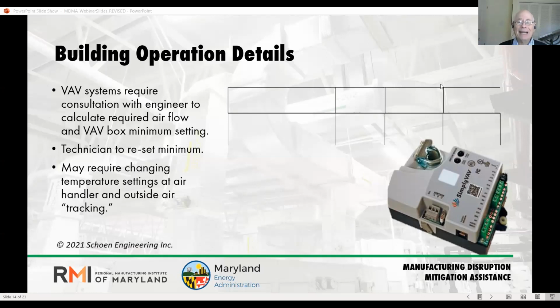It's important to have the settings on these never go to complete shutoff if the thermostat is satisfied. If you go to complete shutoff, that means you have zero ventilation in your room. That's not something we want. So in order to adjust these really takes a skilled technician to properly set it. And it may require changing some temperature settings at the air handlers so you don't overcool or subcool, overheat or subcool rooms. And also may require some tracking at the central air handler.